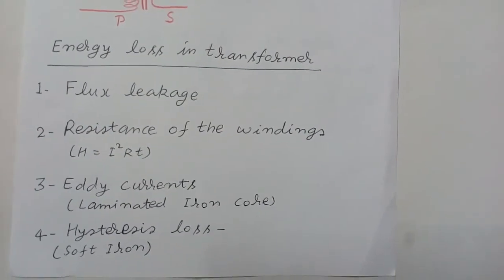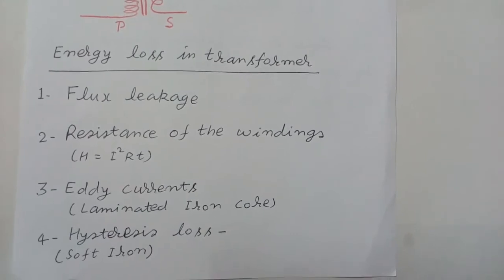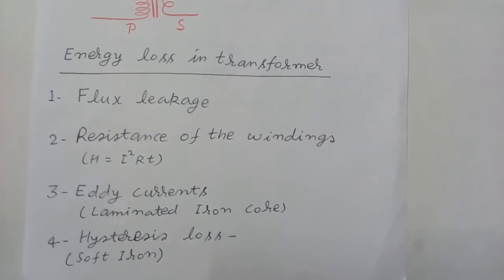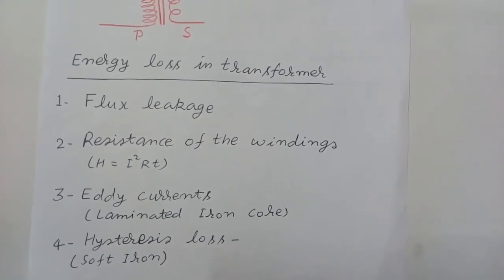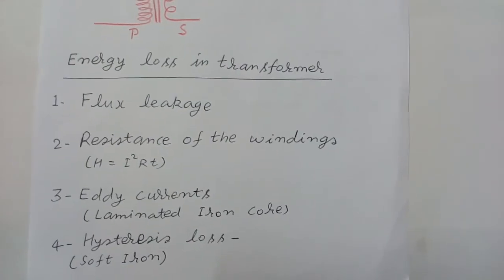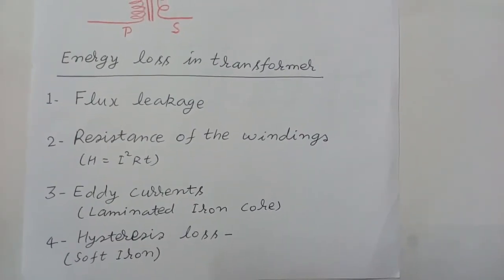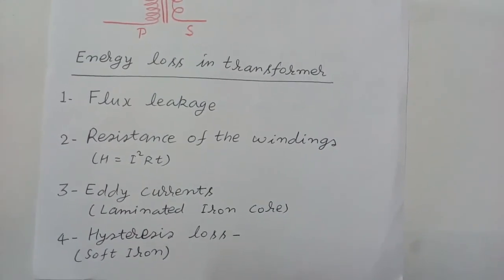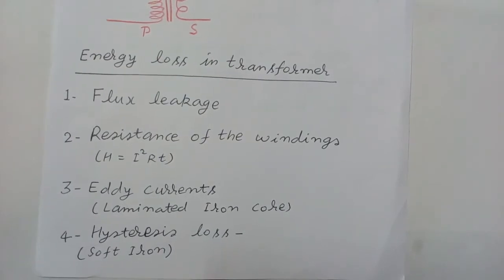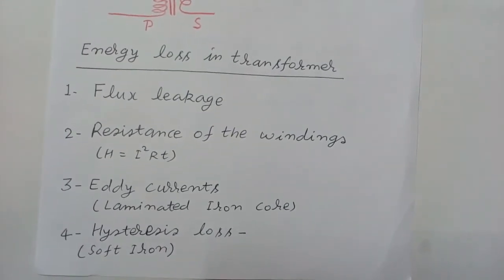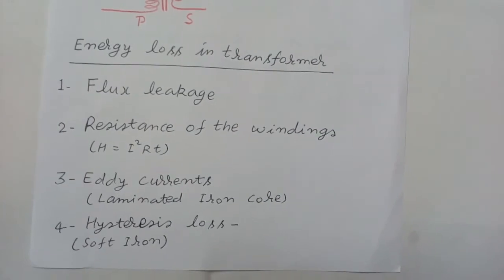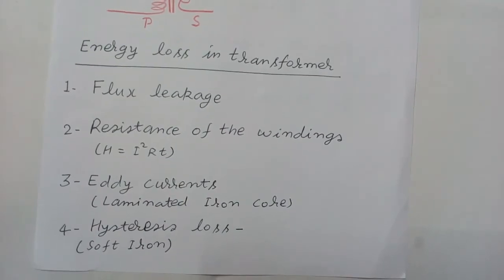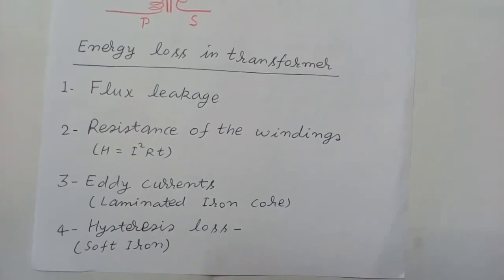We know that the magnetic material used in the iron core in a transformer is continuously magnetizing and demagnetizing and then magnetizing in the opposite direction. So there is a hysteresis cycle, so there is hysteresis loss of energy. For soft iron, this hysteresis curve has less area. So this is the reason why we make the iron core of soft iron.